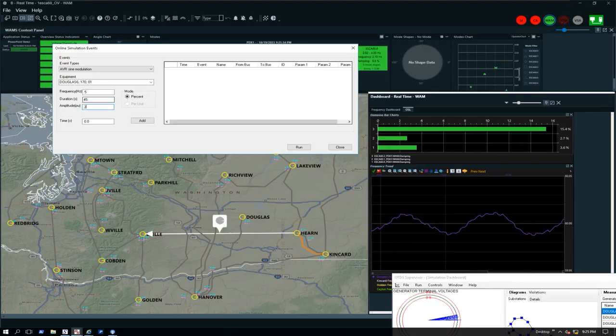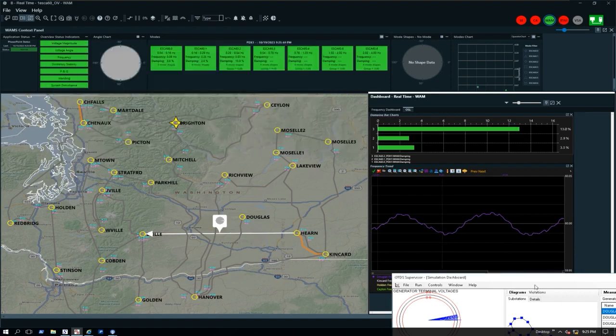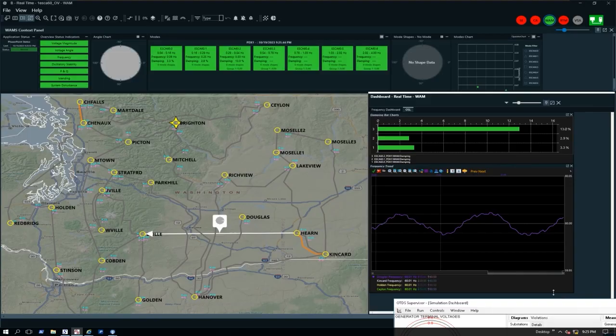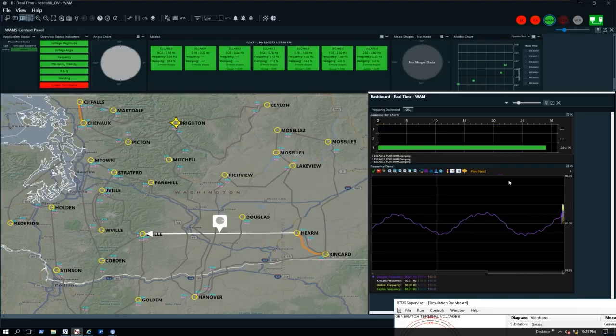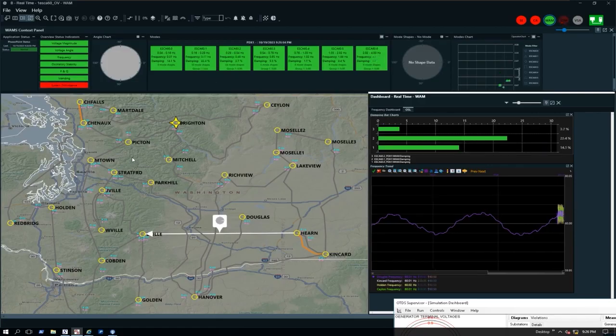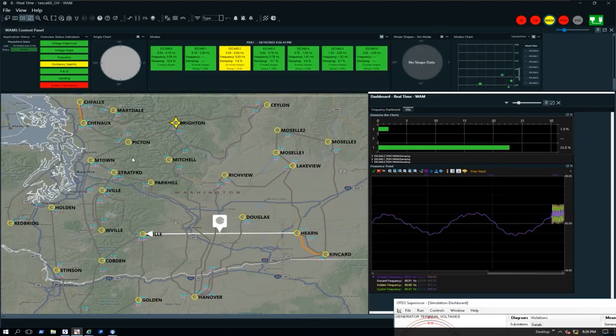And then a 1/4 per unit amplitude. So go ahead and start that oscillation on the grid. You'll see that it starts to show up in our graph here on the right. And then very shortly, our WAMS detects that there's a system disturbance on the system. So WAMS is looking for multiple system disturbances. It looks for line trips and unit trips.